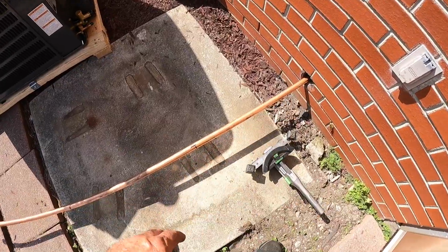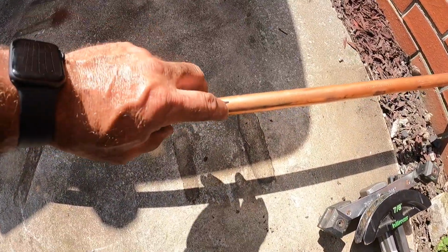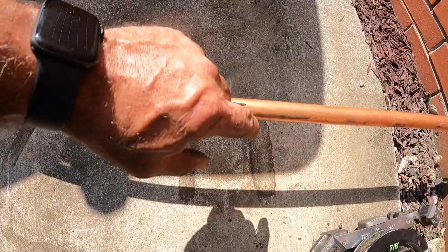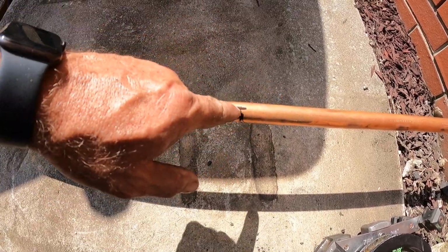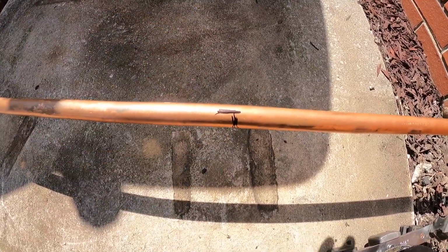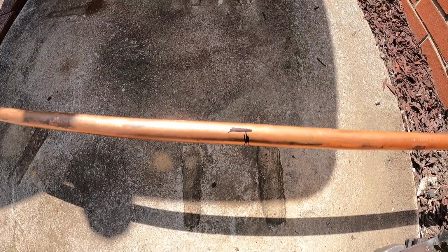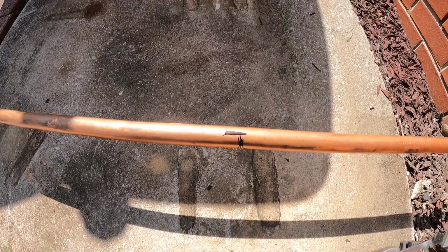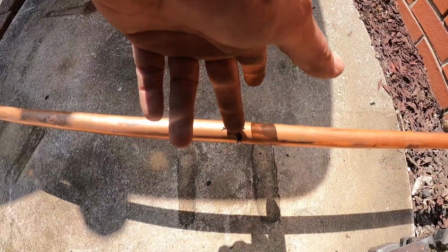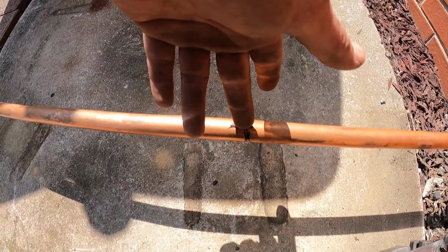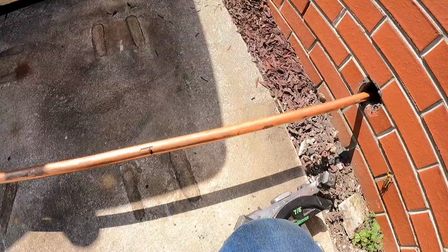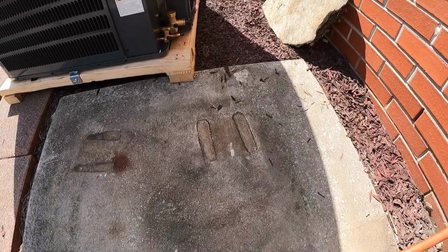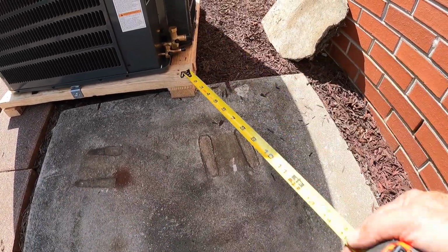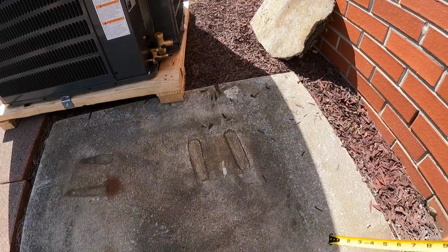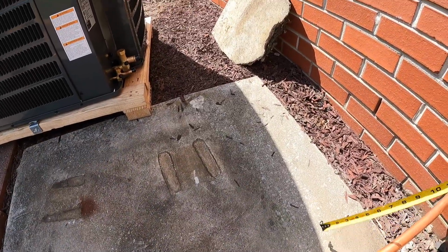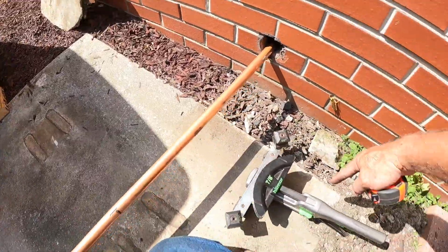Okay, so when it was pushed all the way back and stuck in the unit, I marked where I'd like my bend to come out, right about here. I also marked the top, because when I pulled it out of the unit it tried to move a little. I've got it propped against my ladder right now, so it's still pretty close to plumb, but I need to raise this. I need to be up about 8 and 1/4 inches to the center of it when I put my pump ups underneath, and currently we're about 5, so I need to come up that distance.